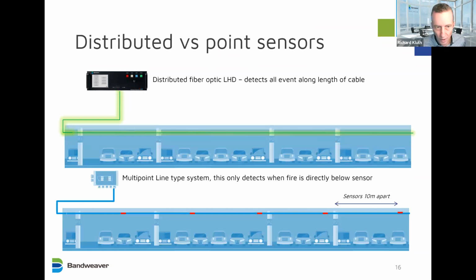I'll just reinforce this point by showing an example of how it works. So if we have a fire at this point in the assets, as you can see, you would measure the quickest at the hottest point above it. We have sensors everywhere, so you get it straight away above here. If the fire starts here, again, you have it above here. And if the fire's here, you get it wherever you are. You can measure directly above it. Means very fast, accurate detection.